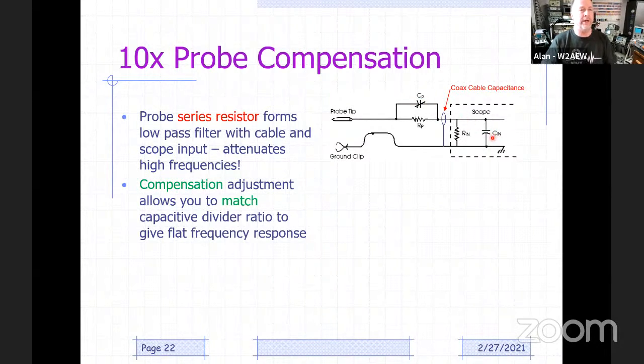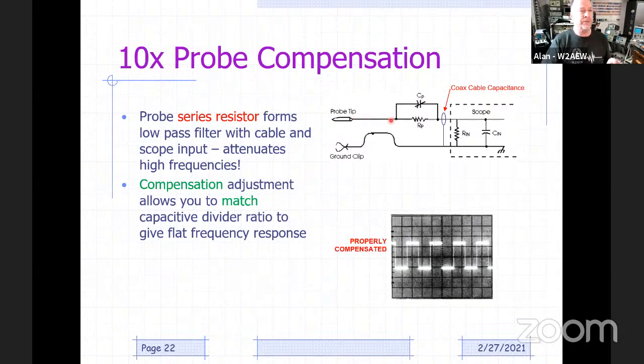In fact, it's the other way around. Instead of 10-to-1 going this way, or 9-to-1 going this way, it's 9-to-1 going the other. But what we're doing is setting up that same ratio. So as the frequency goes up, or at low frequencies, the 10x attenuation is dominated by the resistors. As the frequency gets up past 10 or 20 kilohertz, now the attenuation gets dominated by this capacitive voltage divider between CP, the adjustment capacitor, and the probe's input, the scope's input capacitance.